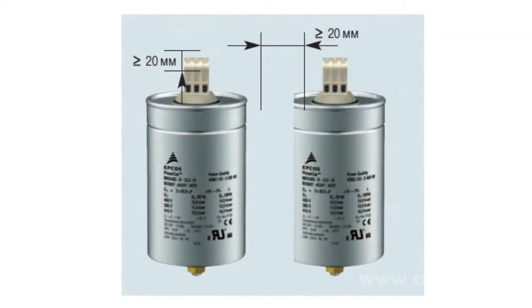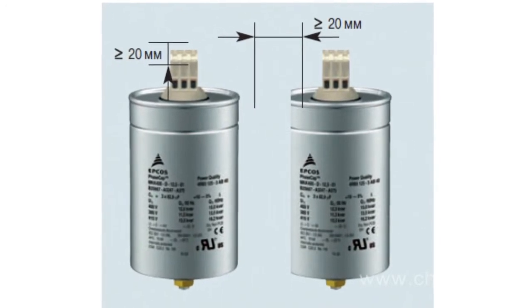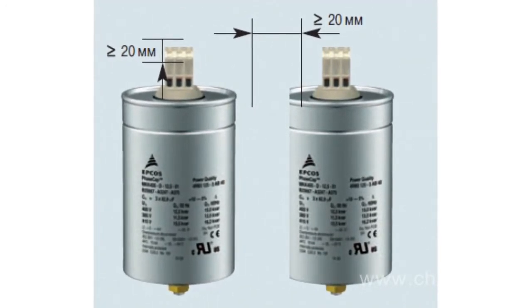The operation of a capacitor under excessive temperatures leads to increased degradation of the dielectric and decreases the capacitor's life. In the vertical disposition of capacitors with a 20 mm gap, the heat dissipation conditions are sufficient, which will reflect positively on the service life of the capacitor.